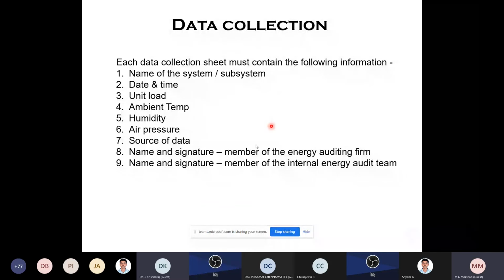I think my presentation is written very clearly, so they should be able to understand. In each data sheet, the name, everything, date and time, then ambient temperature and humidity should be mentioned, because these always have a big impact on the energy audit; ambient temperature and humidity are a very important factor. So these are all the points to be mentioned in the data sheet before collecting the data. Suppose it is a boiler system: you note the load, the humidity on that day, and the time at which you are doing it. After that, you start collecting the data, inlet temperature, outlet temperature, like this. Each and every data set should have an entry like this. Then your data collection will be perfect.